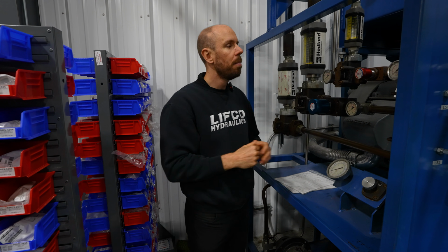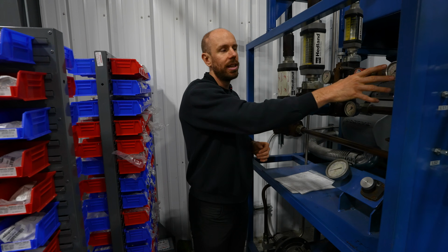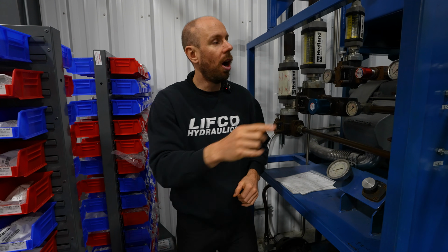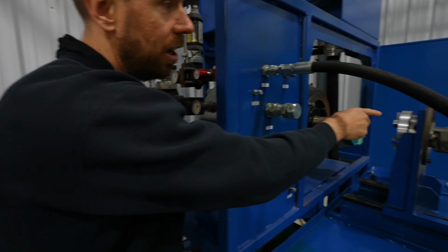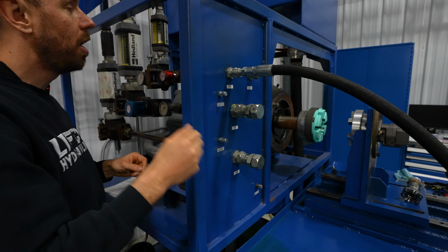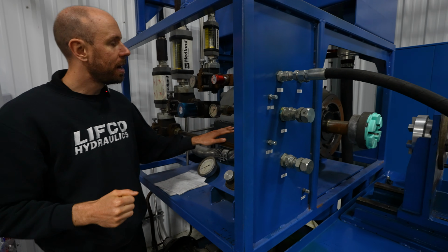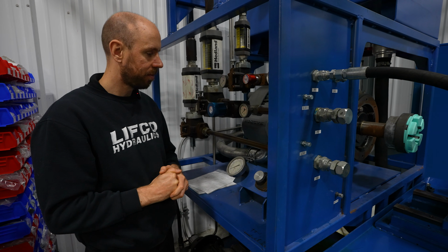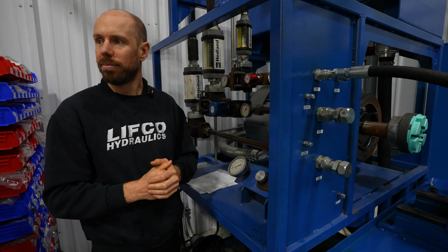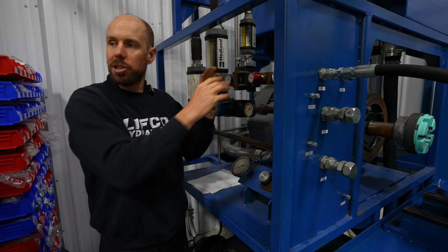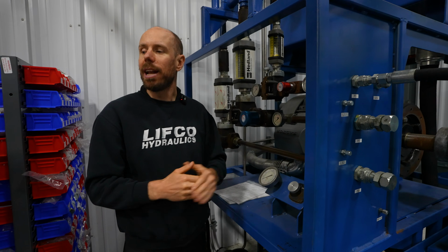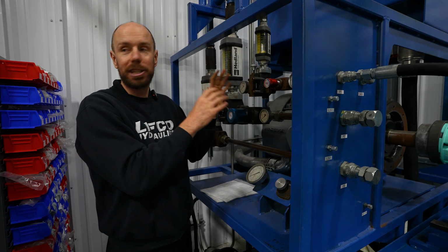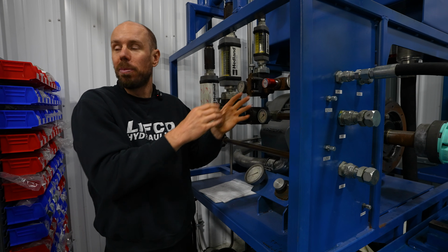And once it hits this pressure, oil being incompressible, basically it's going to happen almost instantly. But it's going to make sure that there is always 2,500 psi in this line, which means that there's always going to be 2,500 on this pump, and which always means that there's going to be a load on the electric motor. Yeah, I see where I was wrong there. Just the flow and PSI difference. Right. And this is where, once you get into hydraulic schematics, you could see that. Because actually you could see on the schematic that it shows it as being normally closed.